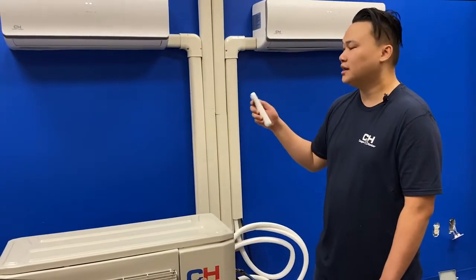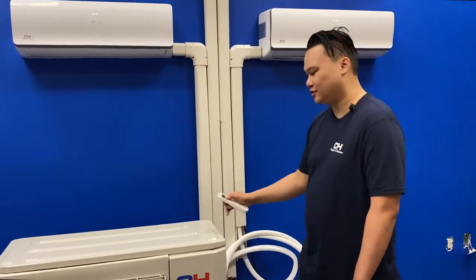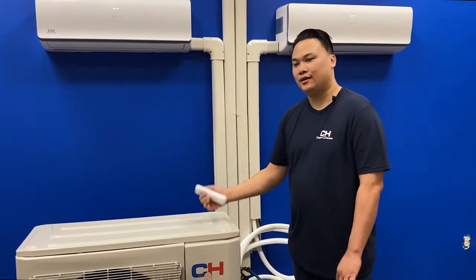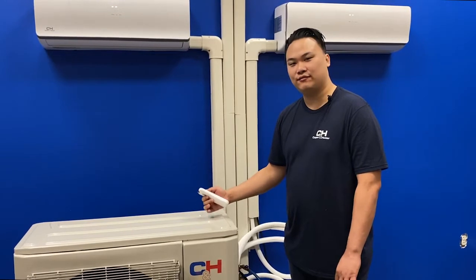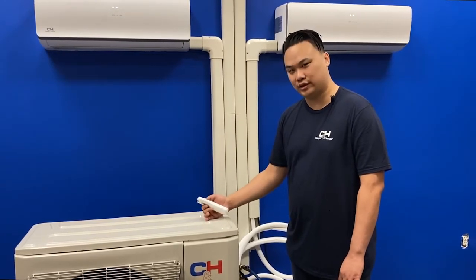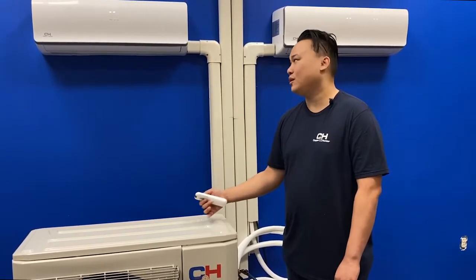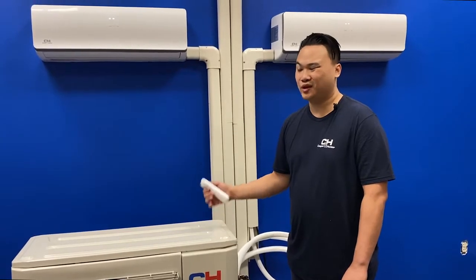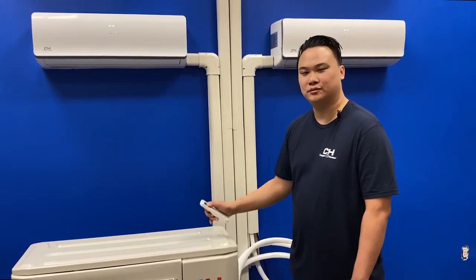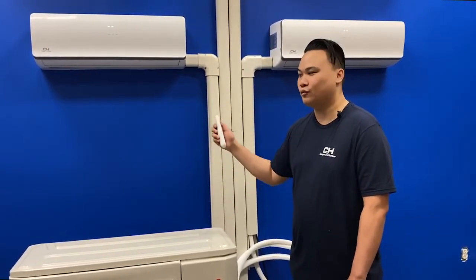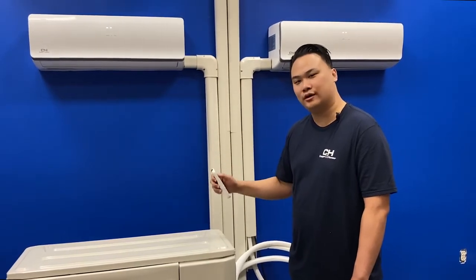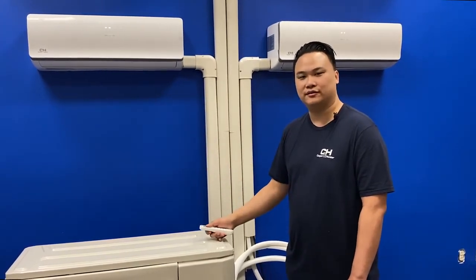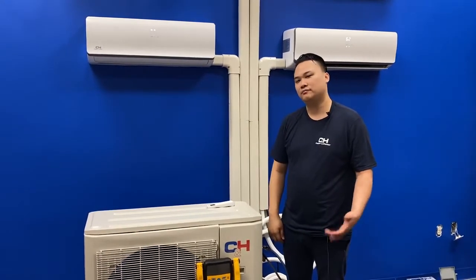It's important to know that because all 3 evaporators are connected to 1 condensing unit, they all have to be set to the same function, whether it be heating or cooling. It's also worthwhile to know, because of this, you cannot set your units to auto, because if one room is colder and the other room is hotter, that's also going to cause a mode conflict. To resolve this issue, just set all the units to the same mode.